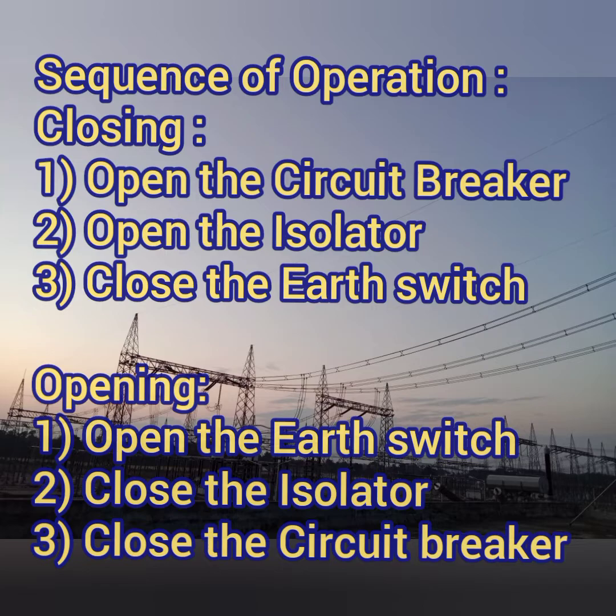For opening, first we need to open the earth switch. After that only, we need to close the isolator. Then at last, we need to close the breaker. This is the sequence of operation.